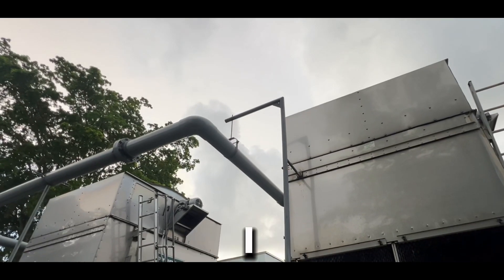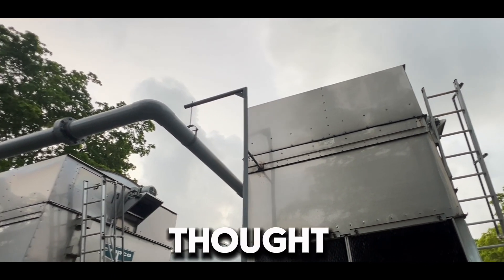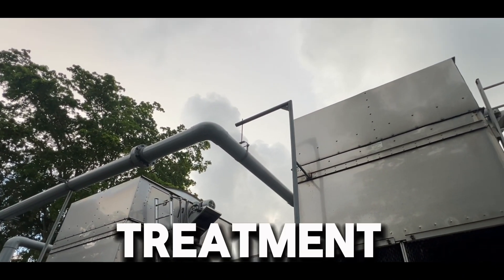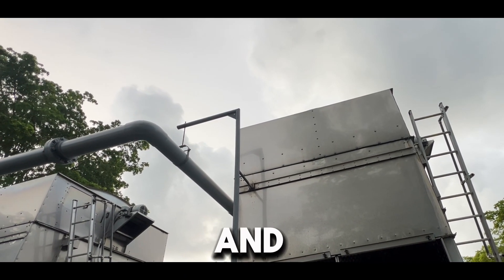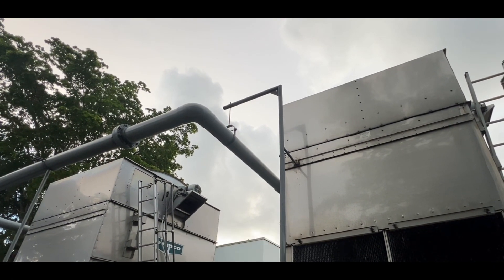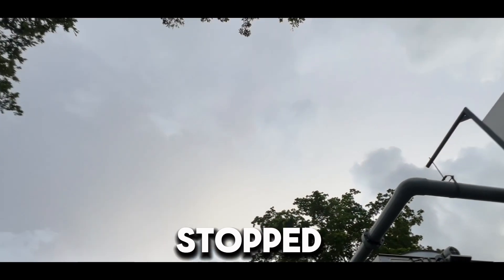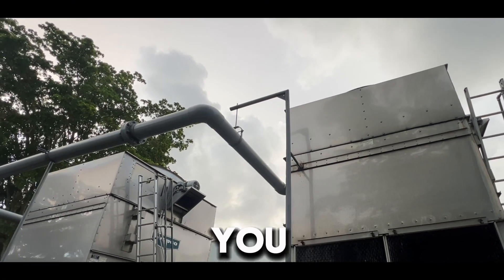Alright, I found out the full story. They came in this morning during the lightning storm and thought something happened to the fans because there was smoke and steam coming out of the top of the towers. Come to find out, water treatment was here yesterday working in the towers — they must have left the drives in hand. They put them back in auto, which explains the high water temp because the fans weren't moving fast enough. Mystery solved. The rain has stopped, the chillers are working. Thanks for watching, catch you in the next video.